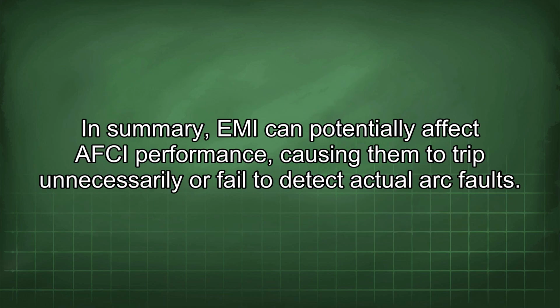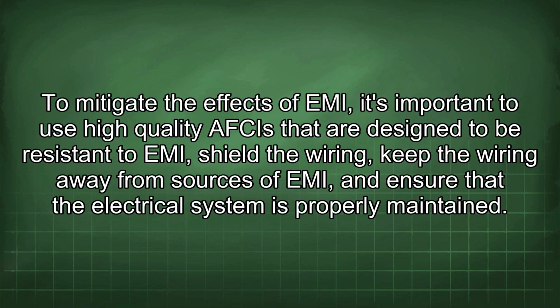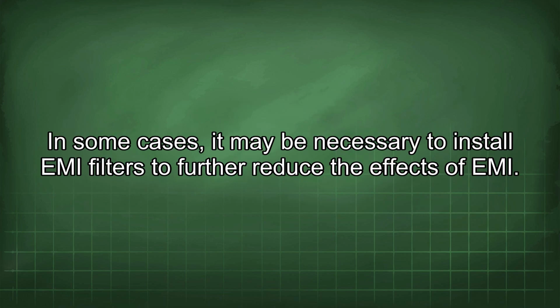In summary, EMI can potentially affect AFCI performance, causing them to trip unnecessarily or fail to detect actual arc faults. To mitigate the effects of EMI, it's important to use high-quality AFCIs that are designed to be resistant to EMI, shield the wiring, keep the wiring away from sources of EMI, and ensure that the electrical system is properly maintained. In some cases, it may be necessary to install EMI filters to further reduce the effects of EMI.